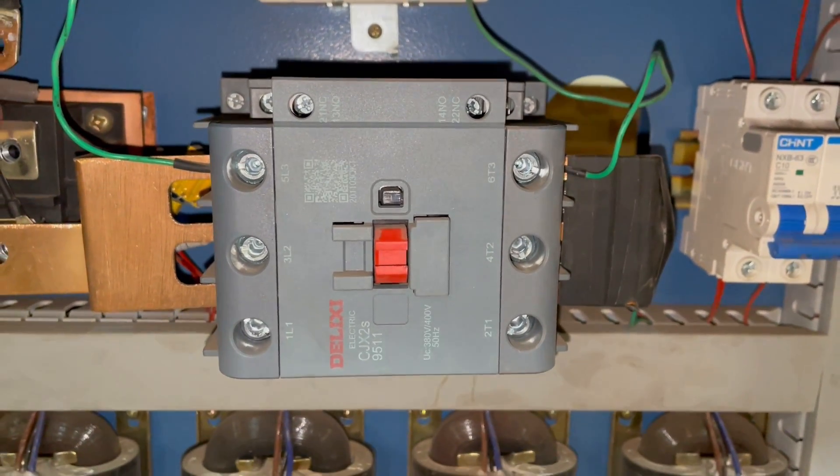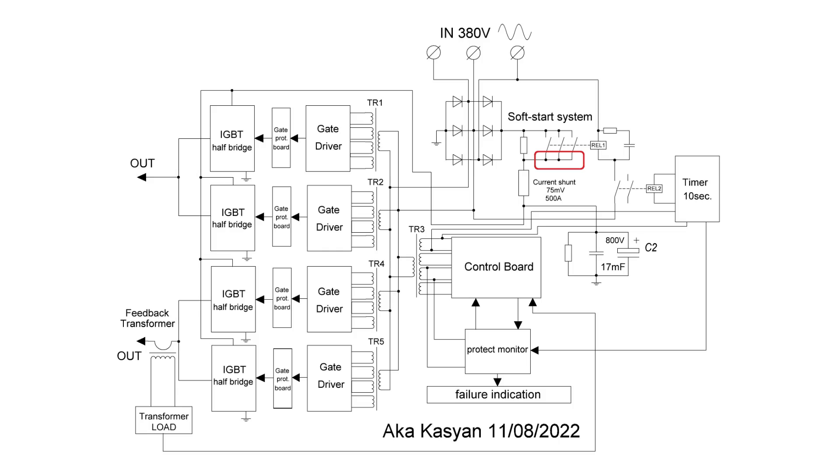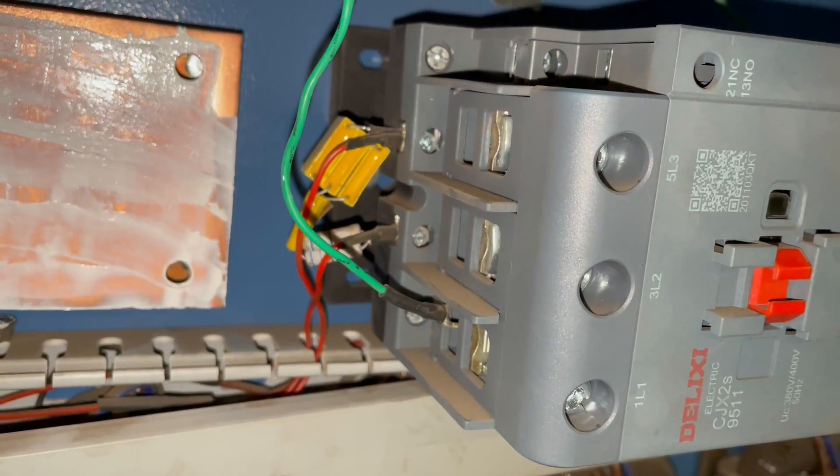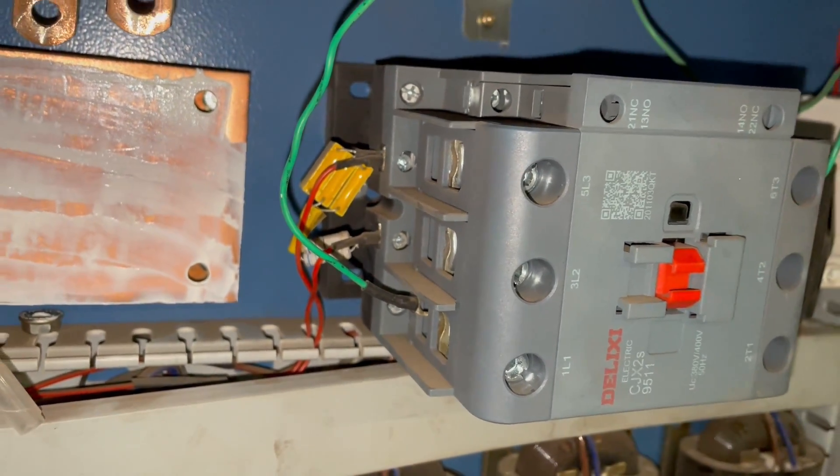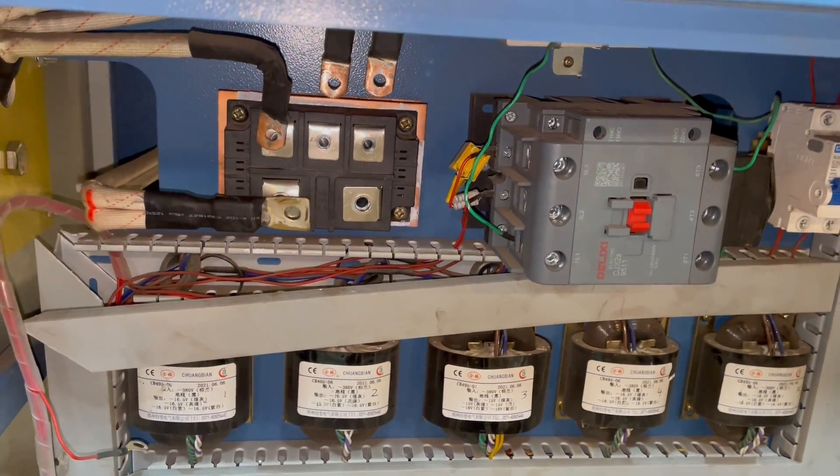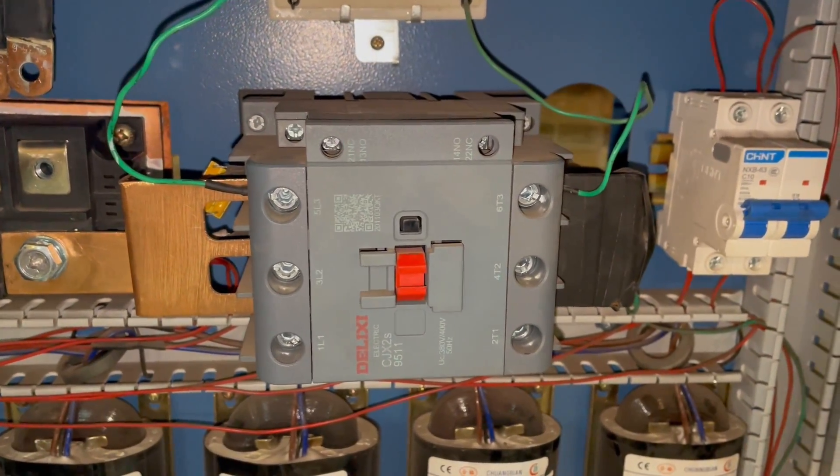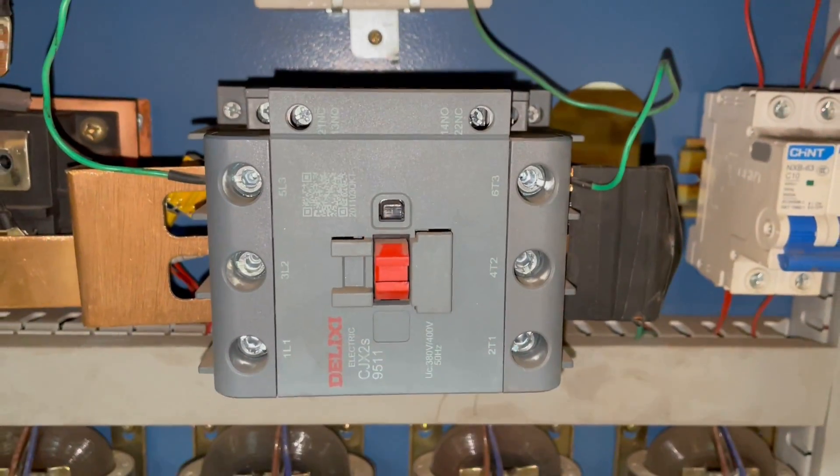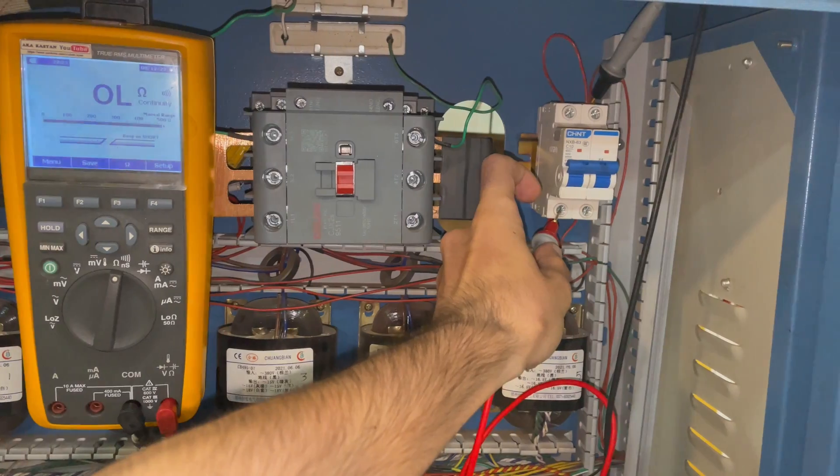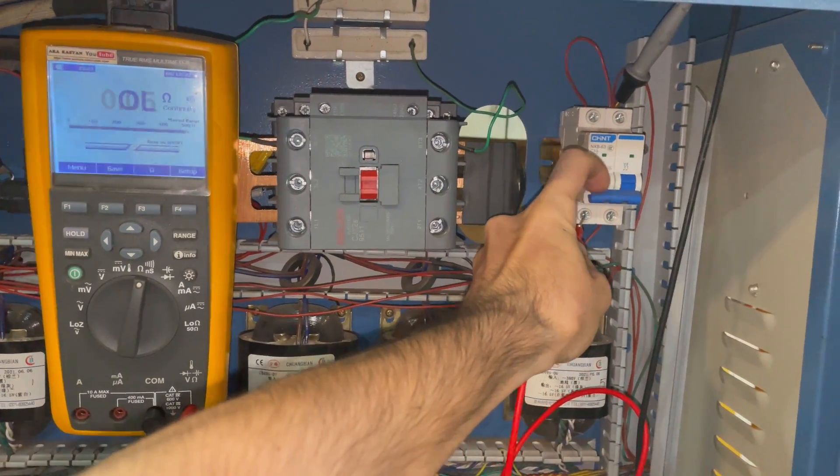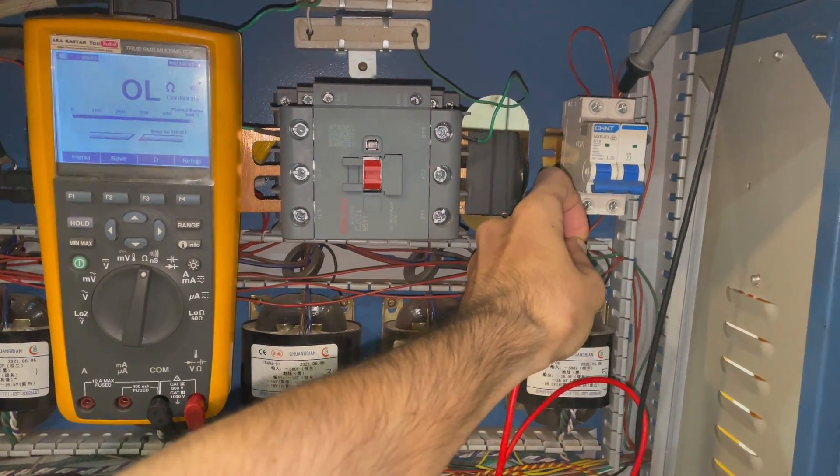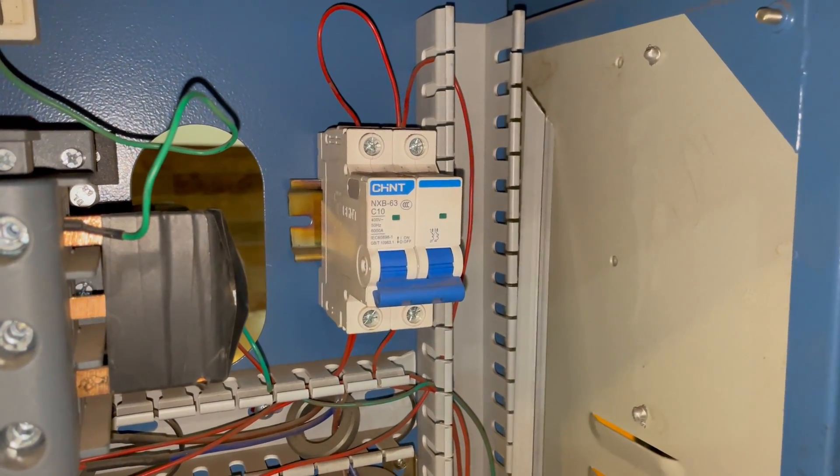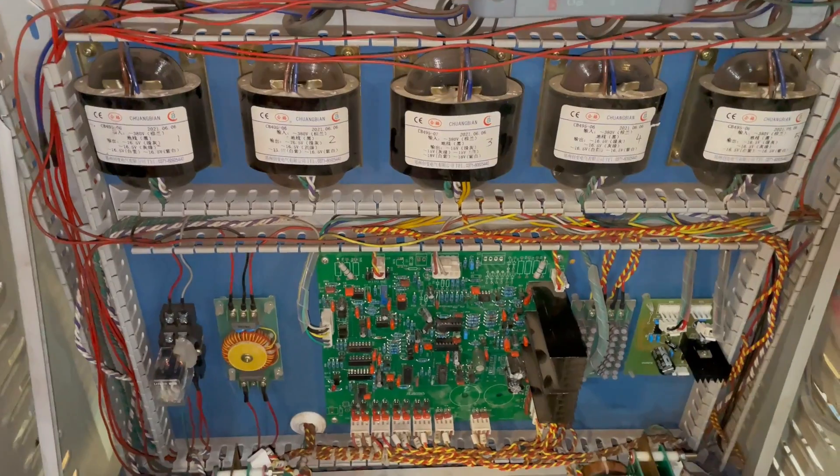Then comes the three-phase starter. All his contacts are connected in parallel and work like a powerful button. A snubber chain is handicraftly fixed on the coil. The coil is intact, the resistance is normal, the starter itself also closes. Behind the scenes the state of the contacts was studied. I'll say that it will serve a long time. Then there is a dual circuit breaker. The checking showed that the node is safe and sound. This isn't surprising, judging by the thin wires from it, there have never been large currents here.